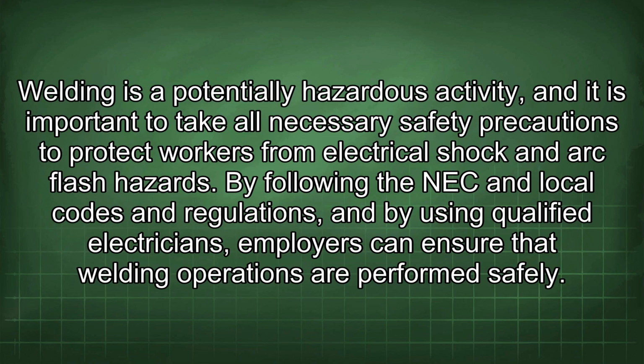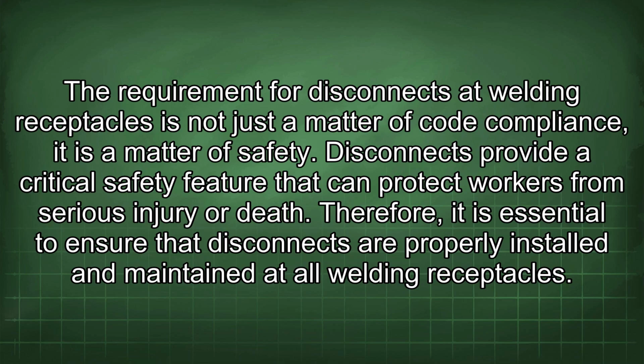Welding is a potentially hazardous activity, and it is important to take all necessary safety precautions to protect workers from electrical shock and arc flash hazards. By following the NEC and local codes and regulations, and by using qualified electricians, employers can ensure that welding operations are performed safely. The requirement for disconnects at welding receptacles is not just a matter of code compliance, it is a matter of safety. Disconnects provide a critical safety feature that can protect workers from serious injury or death. Therefore, it is essential to ensure that disconnects are properly installed and maintained at all welding receptacles.